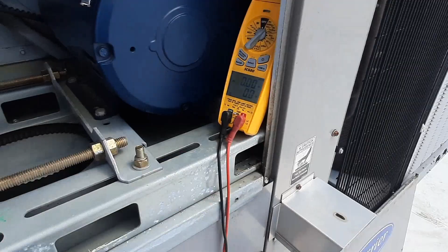So here's what we're gonna do. I have a feeling all these are going to run, but I'm going to do them one at a time just to be safe. I've got coils pulled on everything except the outdoor fan, and this is my 1 and 2 on this side here. I've got only the other one hooked up. We're going to just get an amp draw, kick the power. I should have a call. I only had a 25 amp, not a 30, but hell, they're rated at 0.9 amps. It's almost got to be a direct short that I still haven't seen for that to blow a fuse like that. So let's give it a shot. And I might have to give it a call.